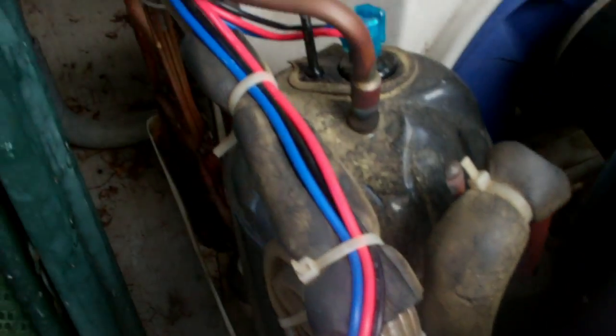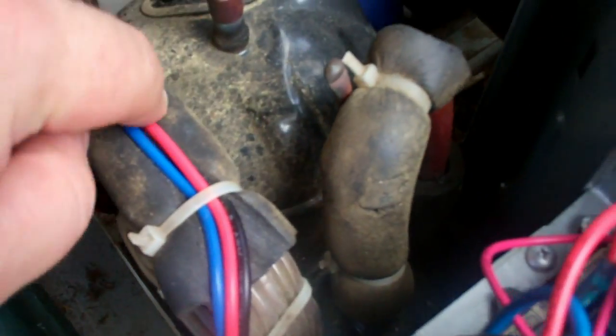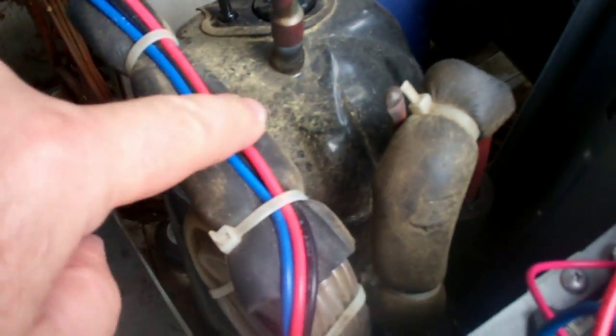Now according to this schematic, it shows an overload relay in between pin number four and the compressor, but it's obviously not there. I don't know why it's listed and was probably not installed.